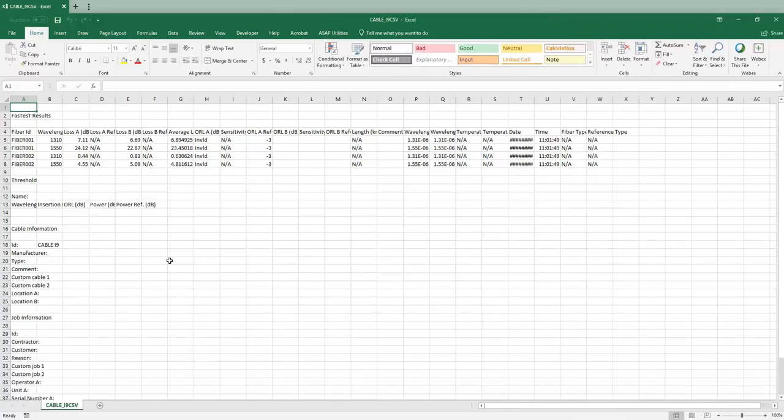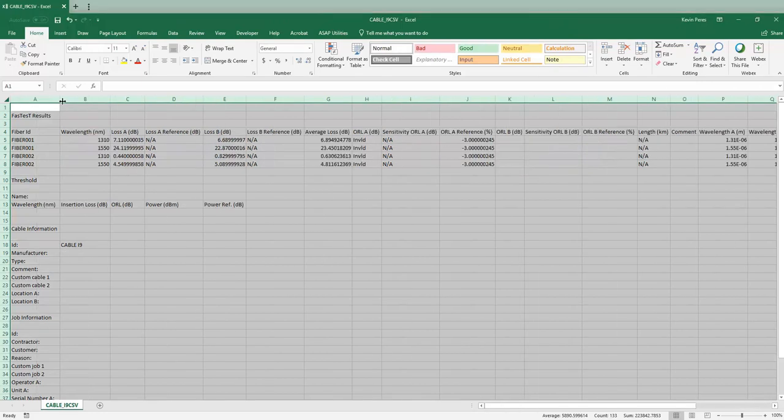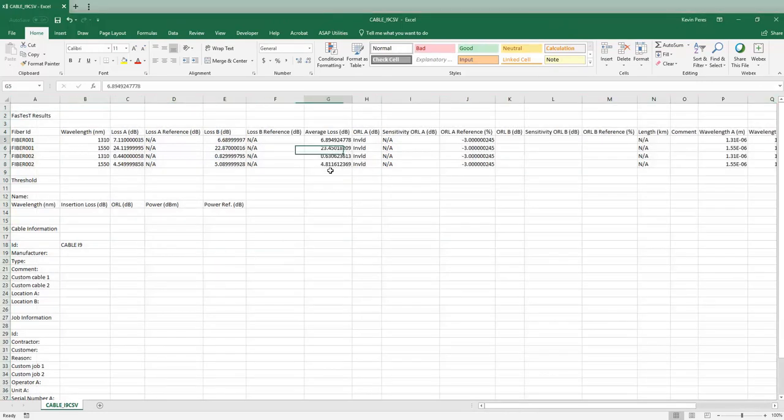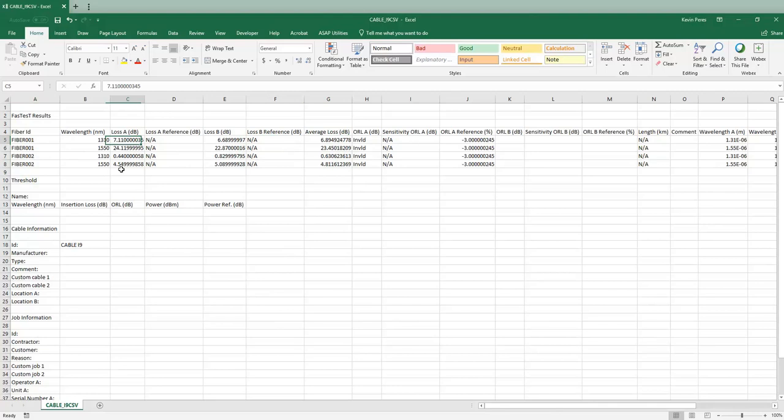And this will open up Excel because it's a CSV. So the first thing I'll do, I'll just highlight all these cells. I'll expand these windows out. So now we see all of our different options here. Average loss is probably the most common one. So there's our two fibers that I tested, both wavelengths.